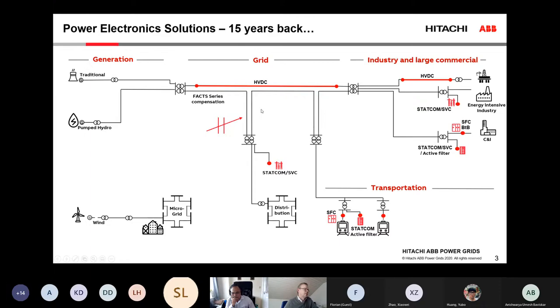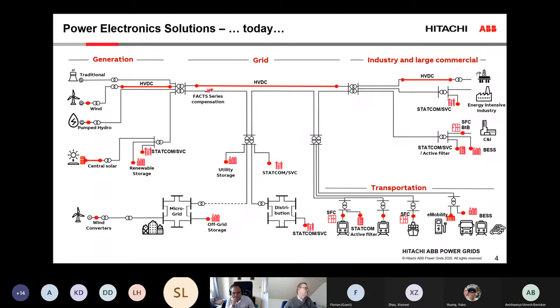But if we see what the grid looks like already today, we have power electronics in a lot more places. We have the wind converters, we have solar converters, we have a product for a variable speed generator where we have a small back-to-back converter to be able to run the hydro turbine at variable speed, and we have a lot of storage in the medium voltage grid, and even on the transmission grid there is energy storage.